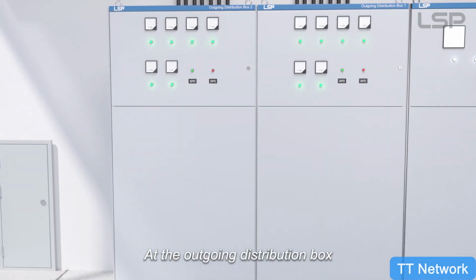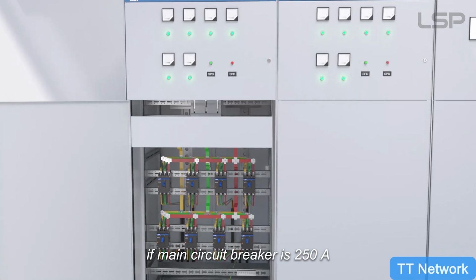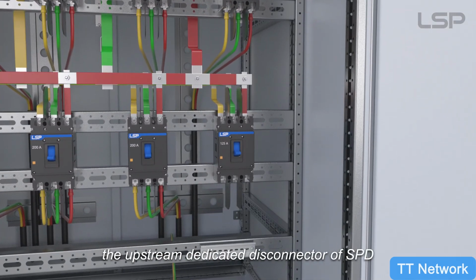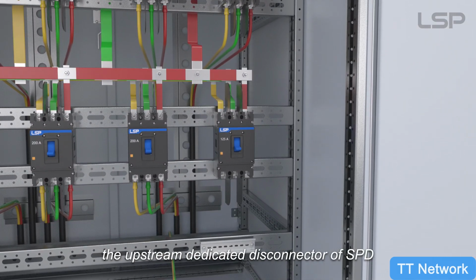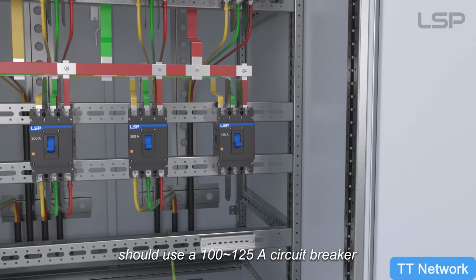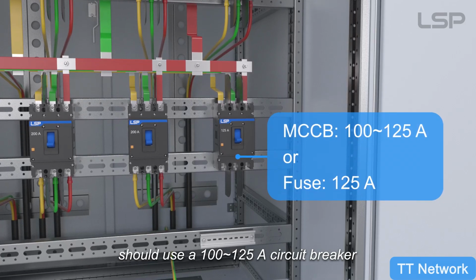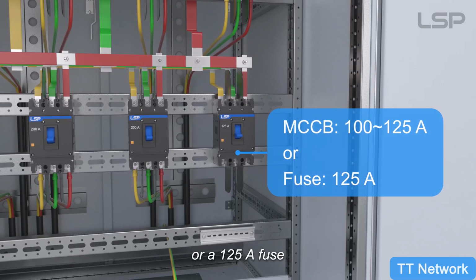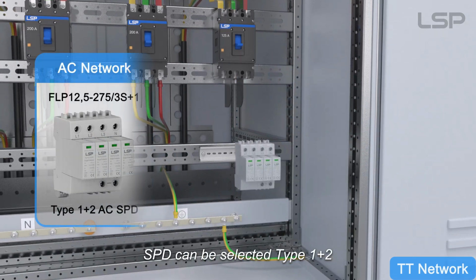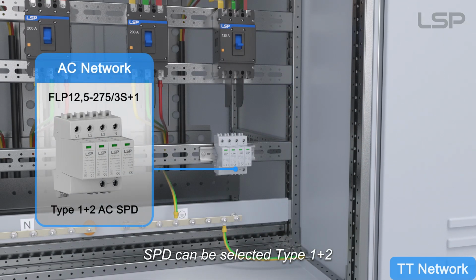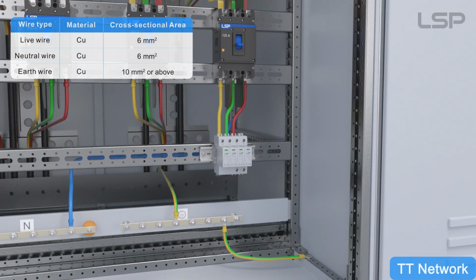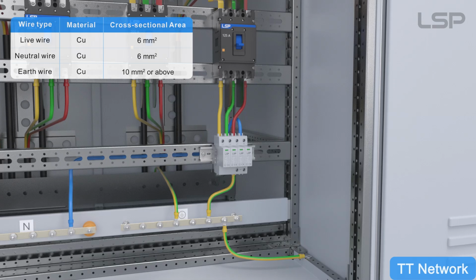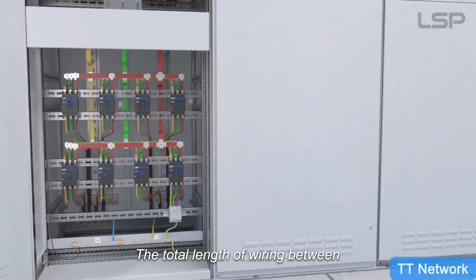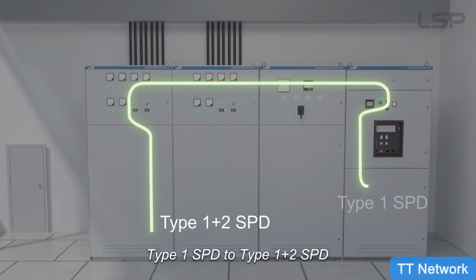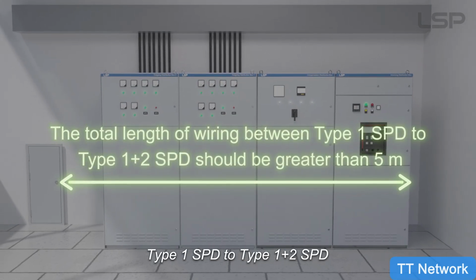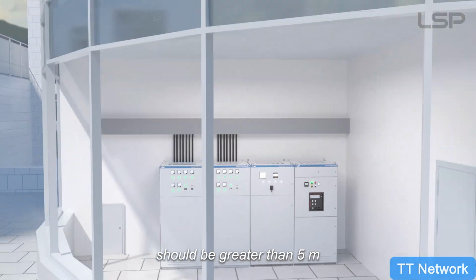At the outgoing distribution box, if the main circuit breaker is 250 amps, the upstream dedicated disconnector of SPD should use a 100 to 125 amp circuit breaker or a 125 amp fuse. SPD can be selected type 1 plus 2. The total length of wiring between type 1 SPD and type 1 plus 2 SPD should be greater than 5 meters.